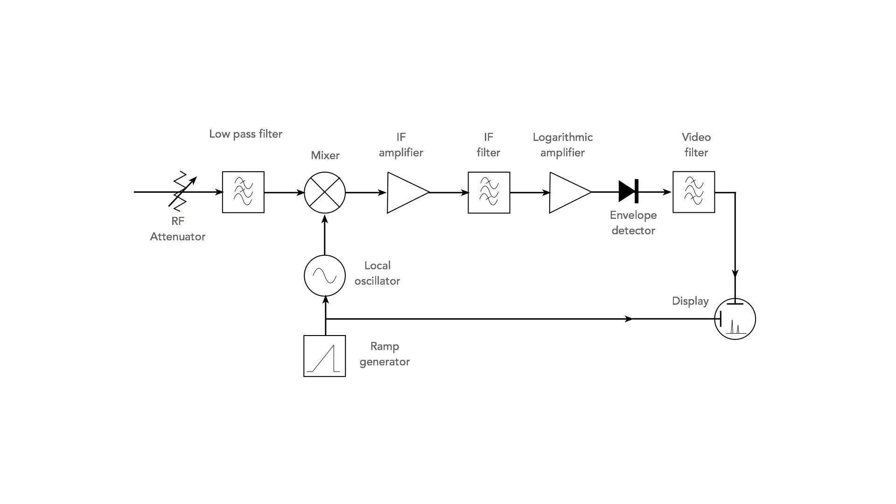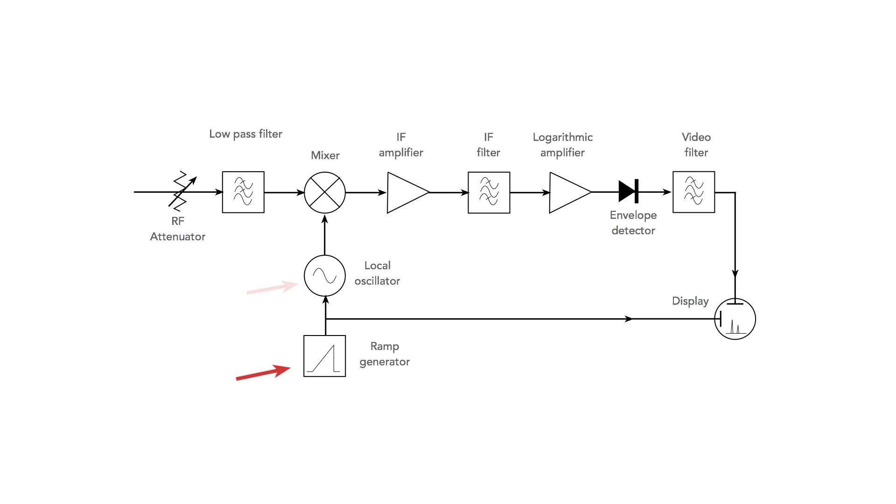Looking at the block diagram we see the signal enters via an attenuator. This is to ensure the signal is at the required level. It is then filtered and passes into a mixer. The frequency of the local oscillator for this is controlled by a ramp generator so that the frequency increases linearly with time. The output from the mixer is amplified and filtered before being applied to a logarithmic amplifier to ensure the output is displayed in decibels.